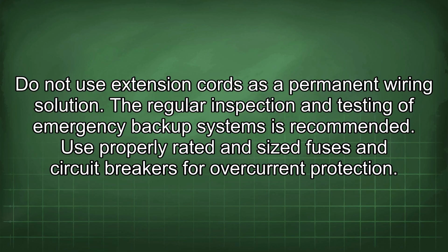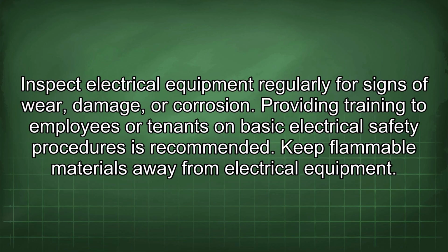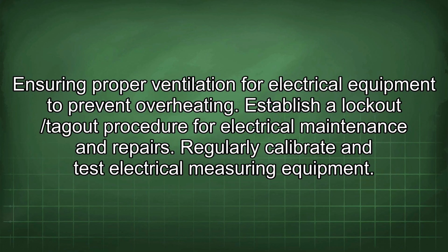Use properly rated and sized fuses and circuit breakers for overcurrent protection. Inspect electrical equipment regularly for signs of wear, damage, or corrosion. Providing training to employees or tenants on basic electrical safety procedures is recommended. Keep flammable materials away from electrical equipment. Ensure proper ventilation for electrical equipment to prevent overheating.